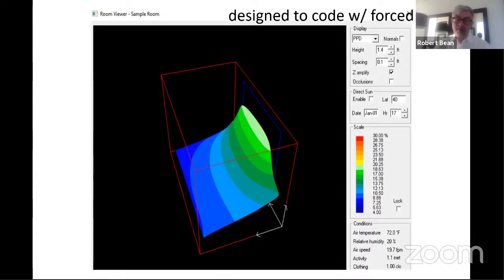As you move further and further away from the glass, the PPD goes down. So the reality in this particular office, in that climate zone, using a code enclosure with forced air, it would not be in compliance. There's very few places in this room, except for the far corner, where someone would actually be comfortable, and that's not practical.